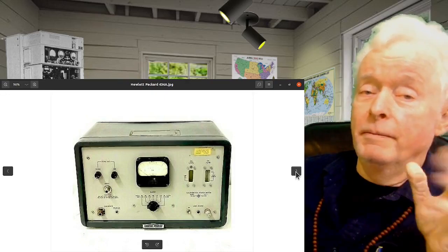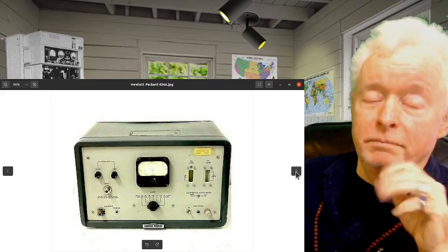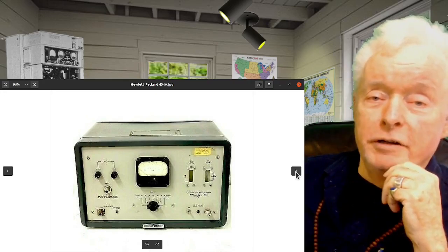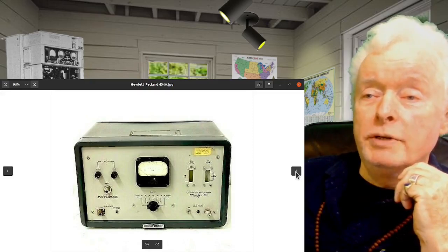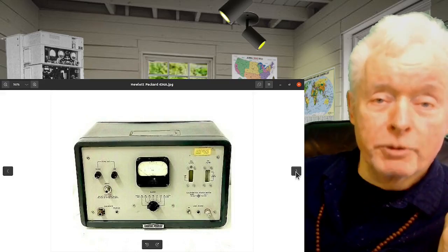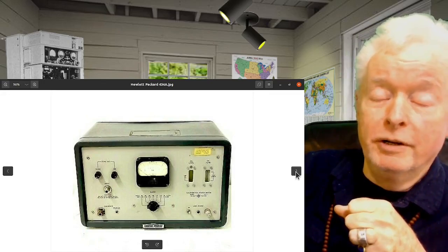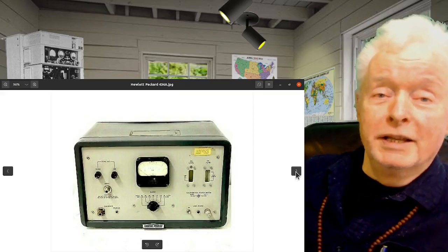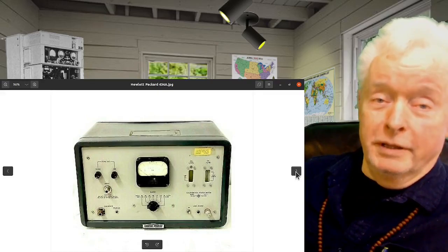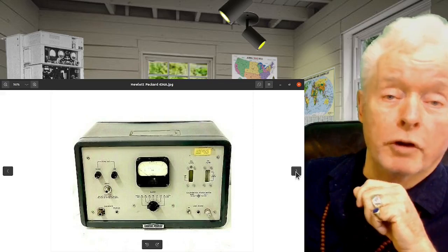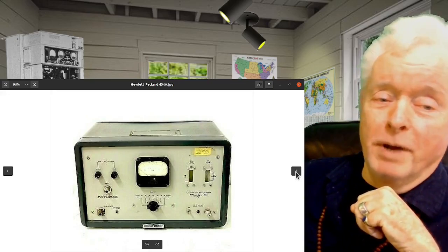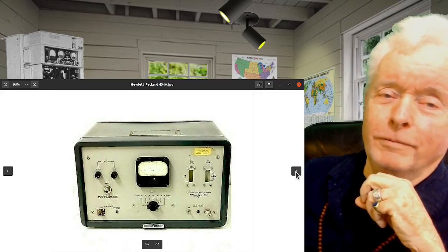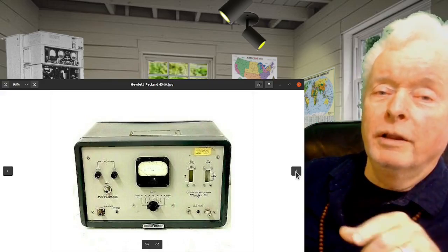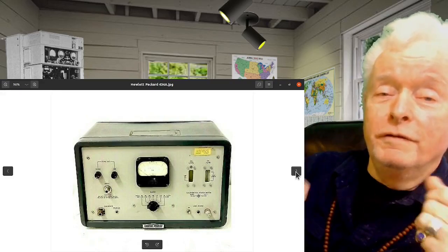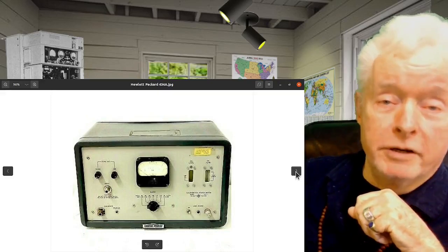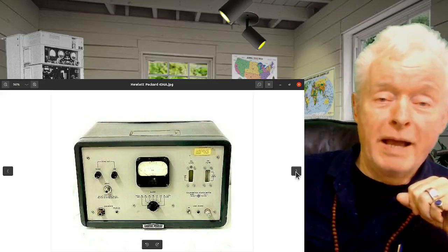This is primary standards laboratory grade stuff back when I was serving. This is the absolute standard for measuring power because it's doing it by measuring two different heat sources. One, your power being applied to a resistor, it's measuring that temperature. And two, its own load that's creating its own temperature that it's also measuring, and it knows to compare to your applied power. This is all done inside this box here. It's a big box. It has some special needs, believe me. One of them is this circulates a special oil past two heat loads to figure out the caloric difference. This is a calorimeter. This measures calories, the ultimate form of power.